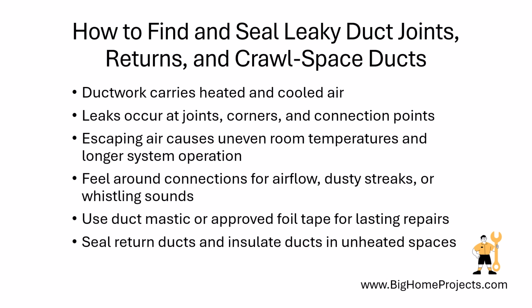A useful test is to feel around duct connections while the system is running and watch for loose insulation, dusty streaks, or whistling sounds. For a lasting repair, use professional duct mastic or approved foil tape, because ordinary cloth duct tape can dry out and fall away.